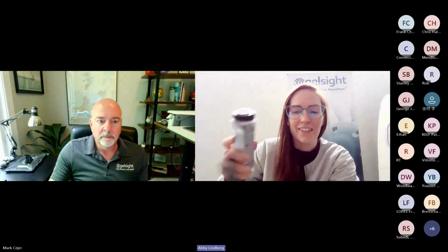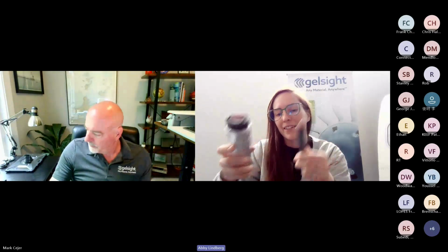All right, in the pit assessment function, what is the maximum pit depth? There are a couple of factors when we're talking about the maximum depth here, and some of it is related to the aspect ratio. Depending on the system, we're looking at about 1 millimeter for the maximum depth that we can measure, for Series 2 and for Modulus with the 16 millimeter here. But that does depend on the aspect ratio.